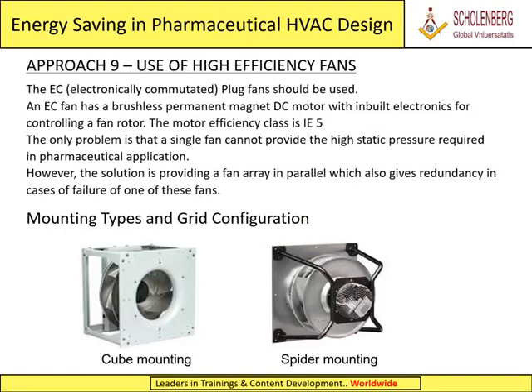Approach 9, Use of high-efficiency fans. The EC, electronically commutated, plug fans should be used. An EC fan has a brushless permanent magnet DC motor with inbuilt electronics for controlling a fan rotor. The motor efficiency class is IE5. The only problem is that a single fan cannot provide the high static pressure required in pharmaceutical application. However, the solution is providing a fan array in parallel, which also gives redundancy in cases of failure of one of these fans.